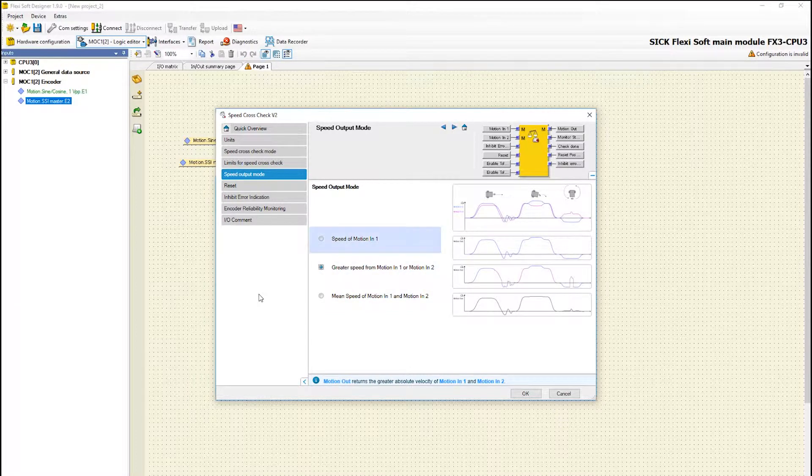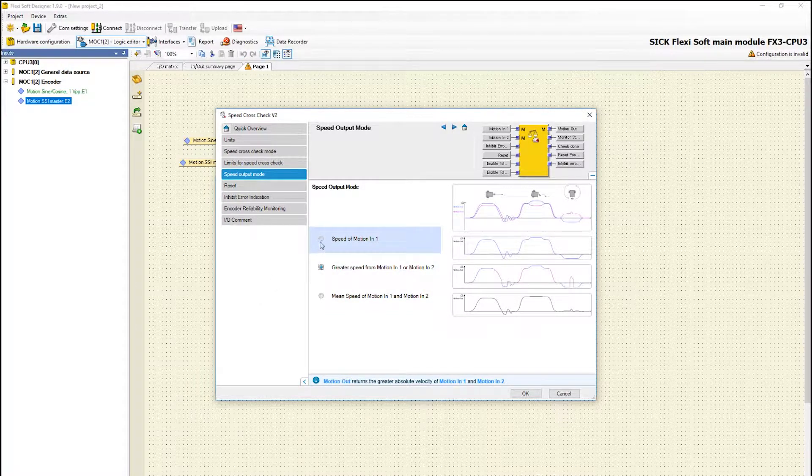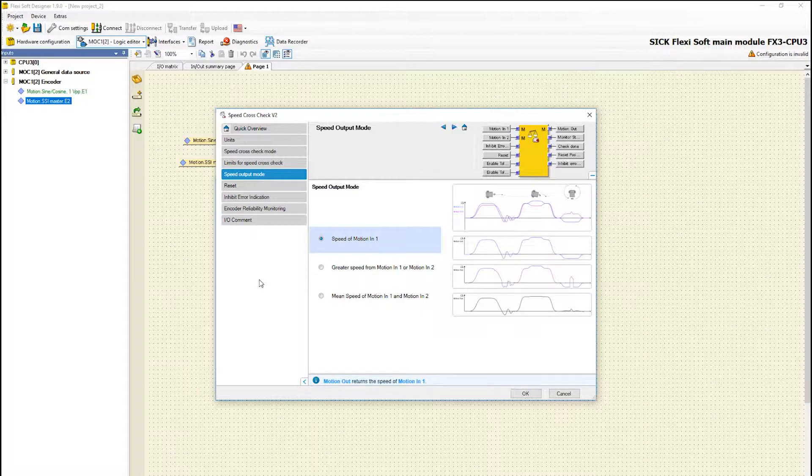Speed output mode with the option speed of motion 1 is usually selected when there is a leading encoder with a higher resolution and a second encoder that is only used for plausibility checks.